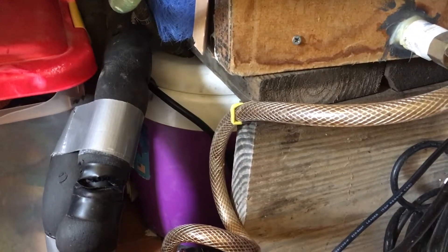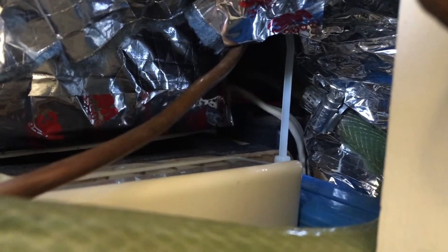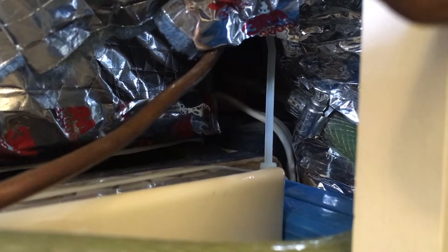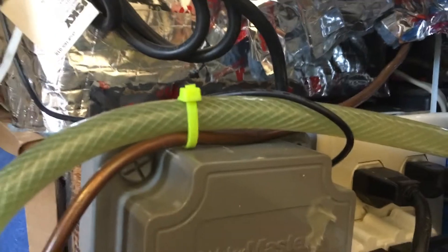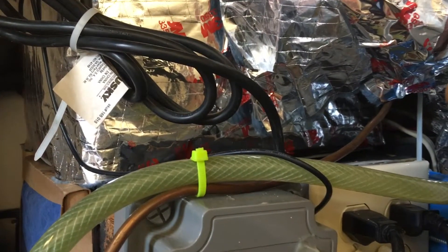Now in here, in this purple cooler, is a pump, and it has water in it. That pump circulates through to an instant hot water heater that would go into the sink in the kitchen. That provides the heat for the water. And then there is a coil mounted horizontally in there that circulates hot water through the coil.